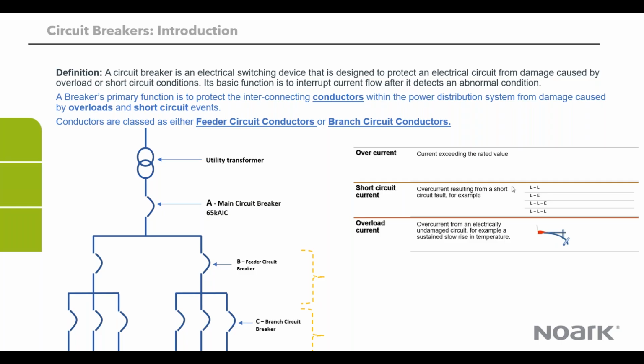And typically you have what we call the line to line. That's two phases coming in touch with each other. You can have line to earth. You can also have two phases with the earth coming together, or you can have a three-phase symmetrical bolted fault. And of all these types of short circuit, the one that is the least common is the three-phase bolted fault, and it's also the most deadly.